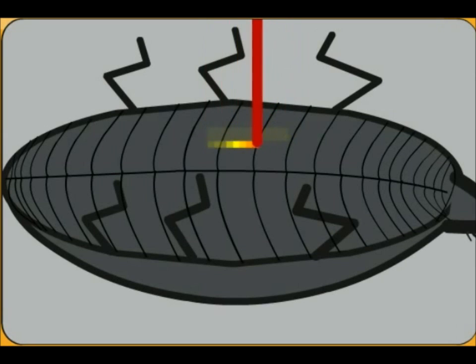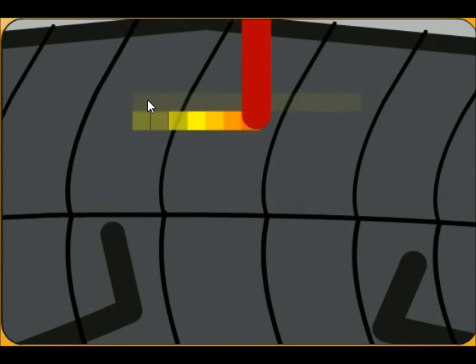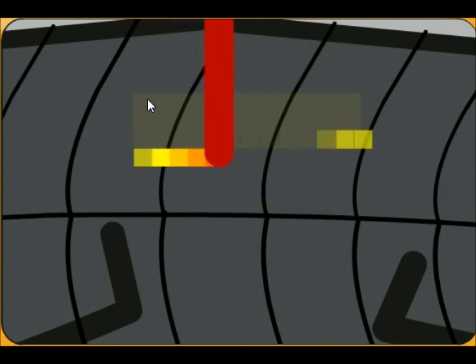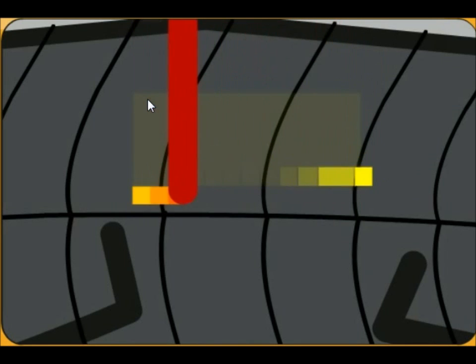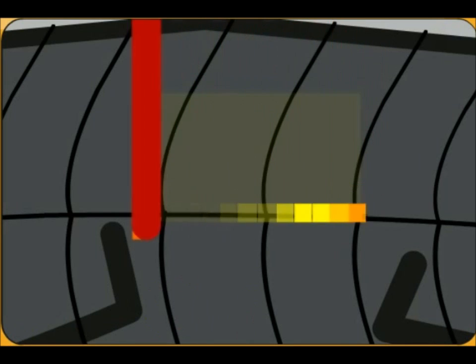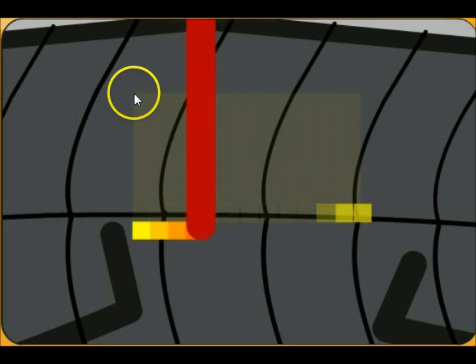So why is it called a scanning electron microscope? Well, as you can see from this illustration, here's our primary beam coming down. And it's actually making the picture pixel by pixel. It's hitting from left to right, top to bottom. And every time it hits, we get electrons from that particular part of the specimen. Interestingly enough, if you want to magnify, all we do instead of actually scanning across a big image like this, we just would scan over a smaller box.